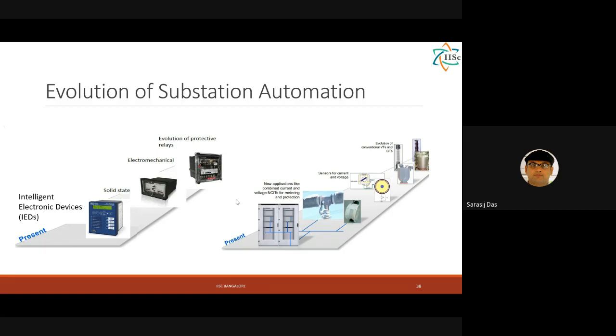From CT and PT also, evolution is happening. The previous current transformers and voltage transformers are being replaced by optical sensors, which are compact, don't need oil, and don't have the problem of saturation. So in future we may see more of these optical sensors rather than conventional CTs and PTs.